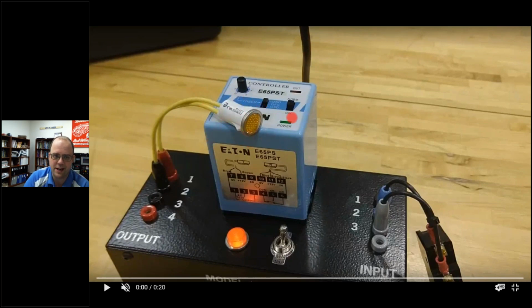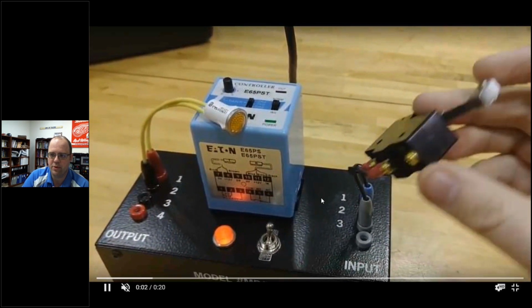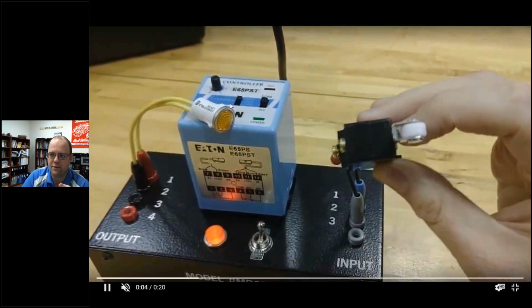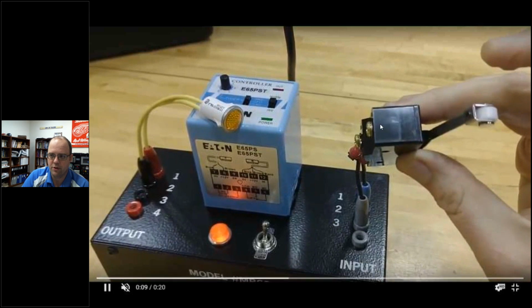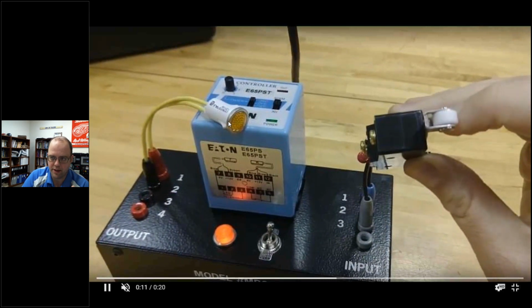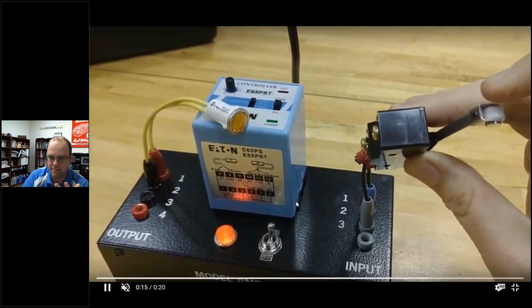In this case, this is a timer that can go both on-delay, off-delay, and one-shot setups. You can see that right here on the switch. But right now, it's set up to be an on-delay timer. And an on-delay timer, as you'll see in a second, is once I trigger an input to the relay, it's going to time for the 3 seconds, and then the light's going to turn on. And then once I release the input, the light drops immediately. So input, time, then it turns on, hence on delay.